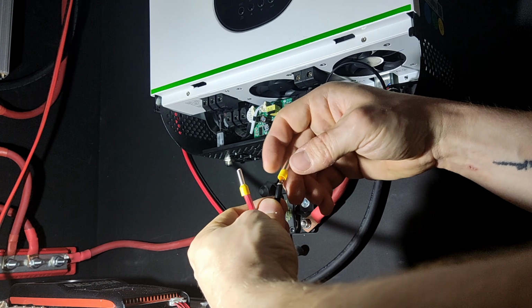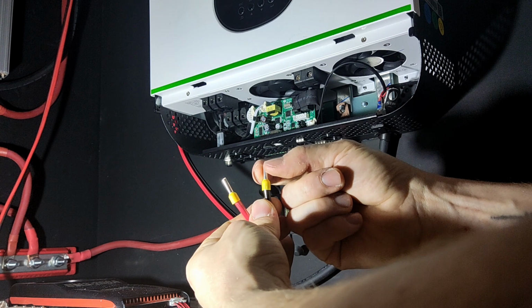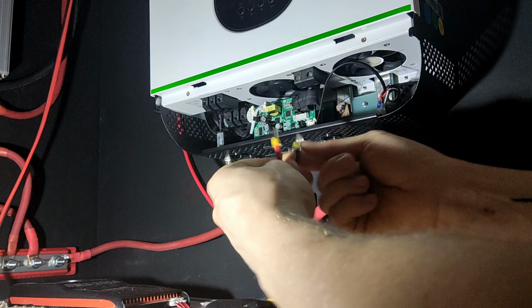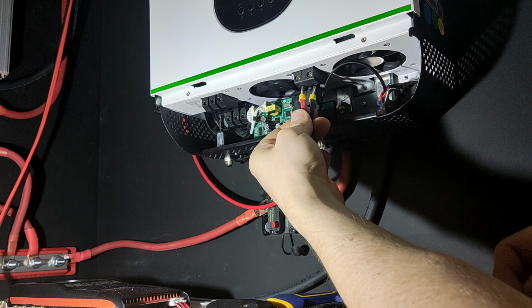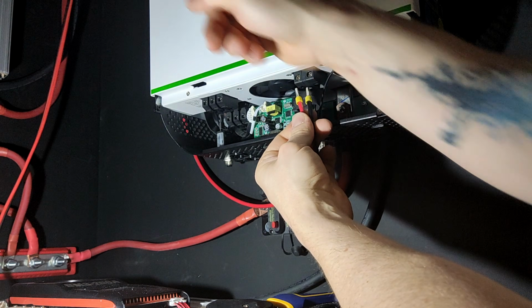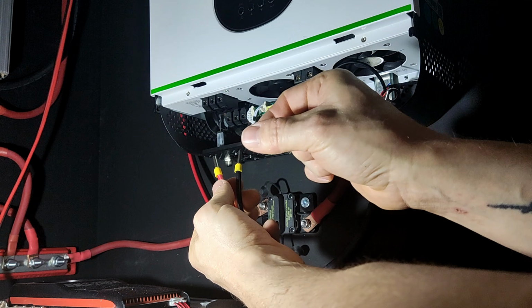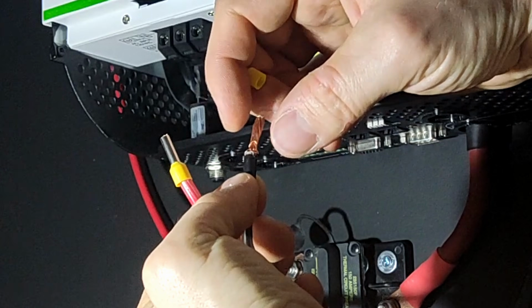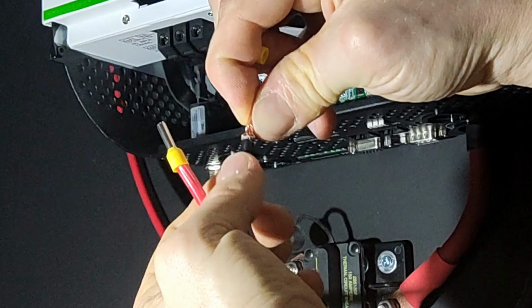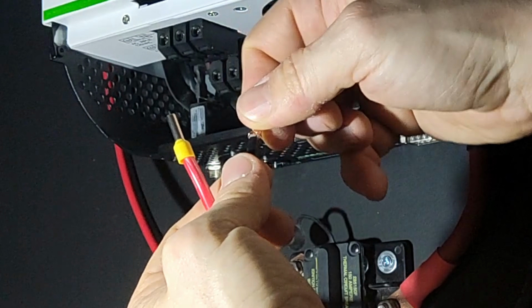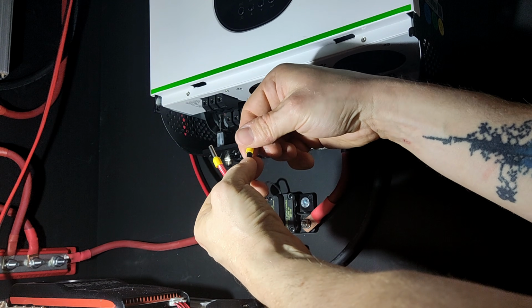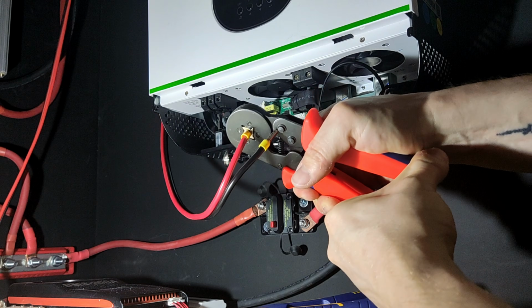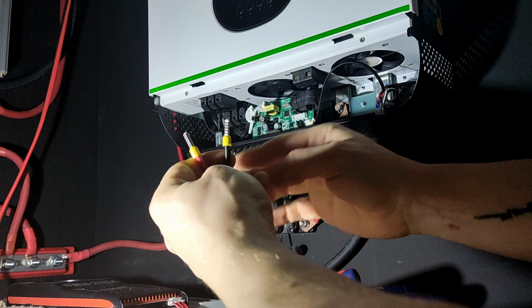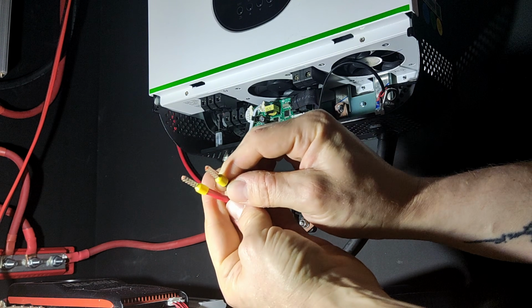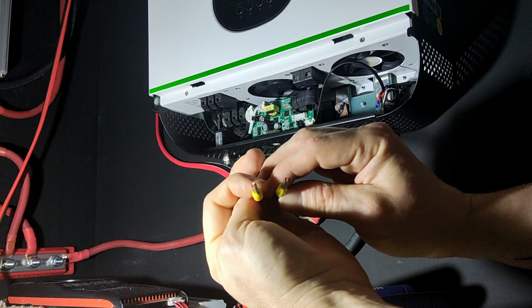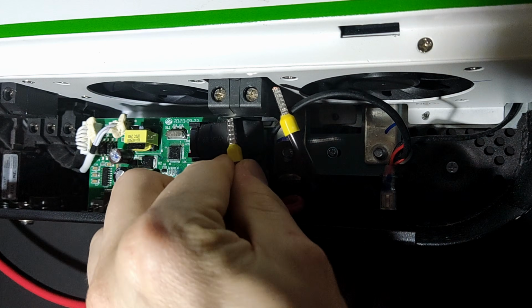Now, the purpose of these ferrules is to keep the individual strands of the wires compacted together as they get placed into the compressive outlet here. Because both here and on the breakers, it's a screw compressive fitting, where if this ferrule wasn't here, it would just be smashing these individual strands in there over time as it vibrates, wiggles, whatnot. It's not going to stay together very well. Safe and reliable. So instead of a bunch of wild strands just smashed together, we've got two nice square strands that will have good contact.